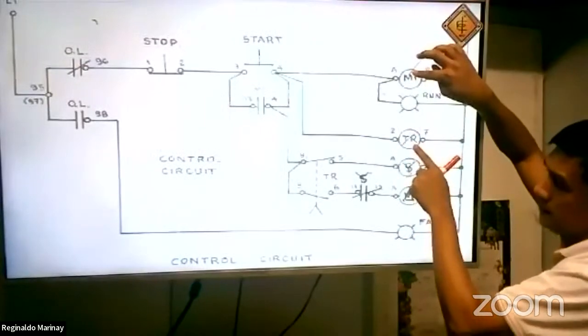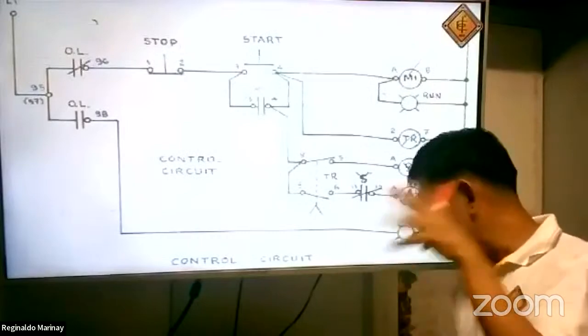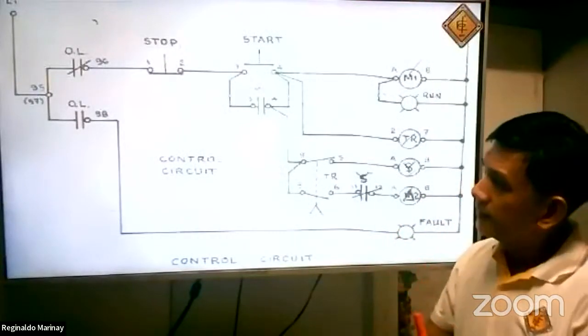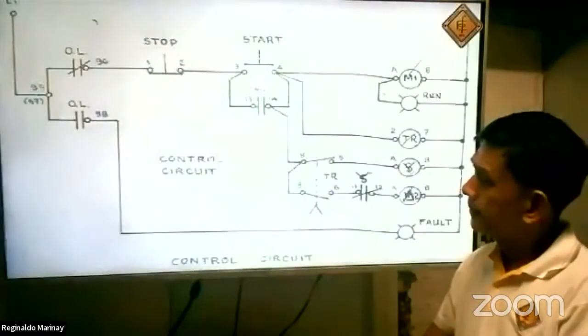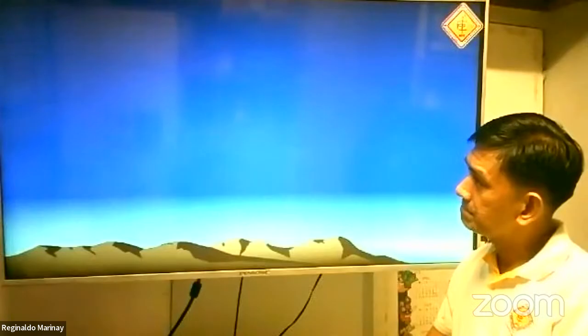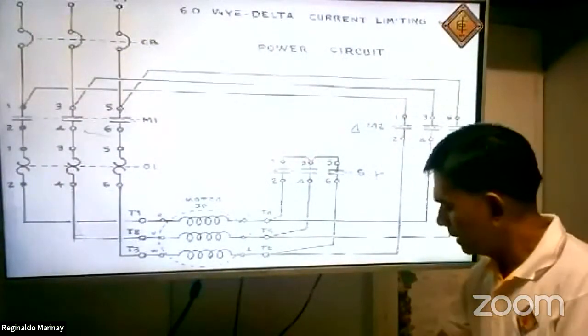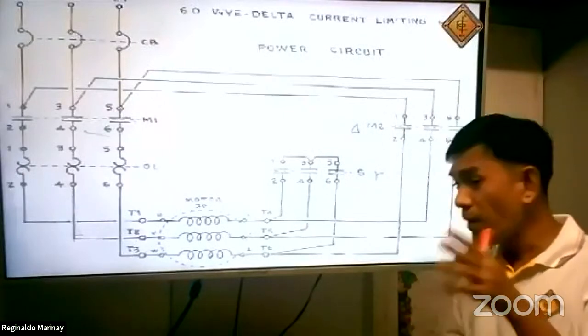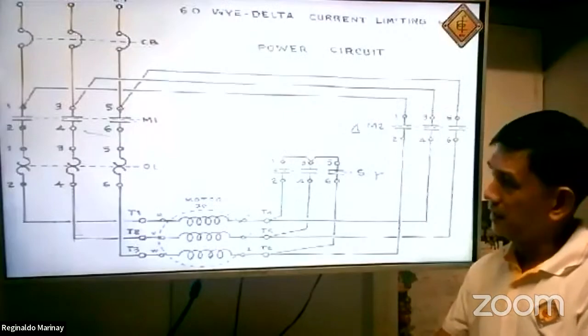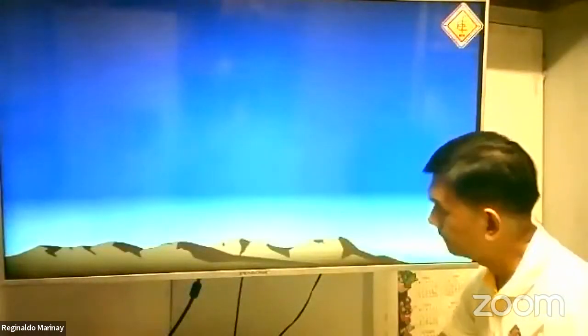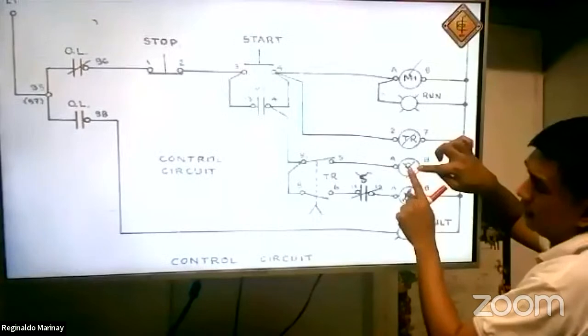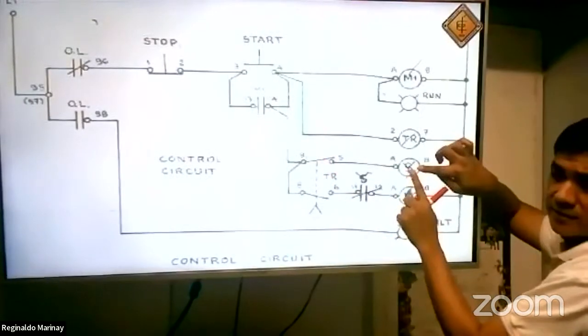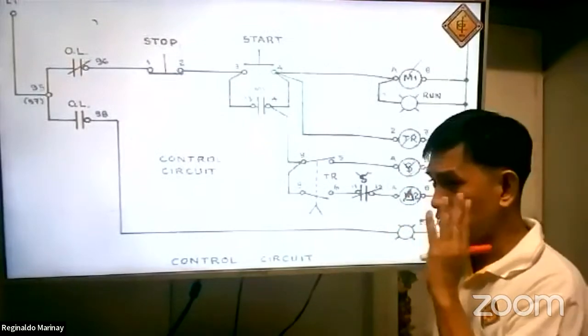That is your setting. What will happen from 0 to 2.99 seconds? Remember that initially, the Y contactor becomes energized. Let's take a look again. From 0 to 2.99 seconds, the Y contactor holding coil is being energized. See? That becomes energized, the Y contactor.